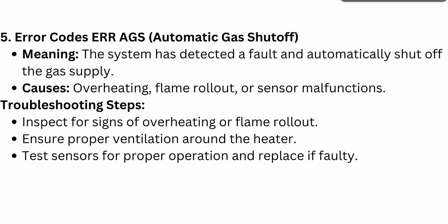Another error code is ERR AGS — automatic gas shutoff. It means the system has detected a fault and automatically shuts off the gas supply. Causes can be overheating, flame rollout, or sensor malfunctions. This is a safety measure. To troubleshoot, inspect for signs of overheating or flame rollout, ensure proper ventilation around the heater, and test sensors for proper operation, replacing any that are found faulty.